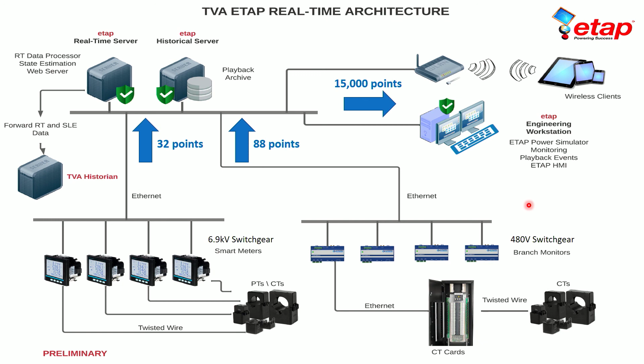What I think is really cool about this is when you add up all these voltages and currents, we're talking about 32 points coming from the 6.9 and 88 points coming from the 480, so about 120 points total—that's all I'm sending. The advantage of using a system like ETAP RT versus any online monitoring system is that by using the digital twin concept, having that operational model coupled with these data points, we're able to realize 15,000 points. We get the whole system—all the power flows between all the buses, all the currents, all the breaker positions. That's phenomenal, and I think that's the main advantage in our industry for using an ETAP RT system over just installing online monitoring of selected points.